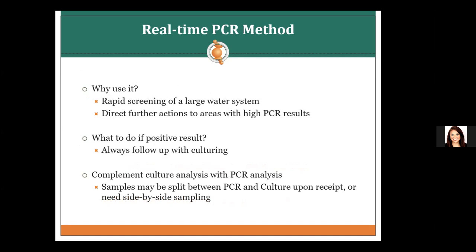People still use the PCR method because it is a rapid screening method for large water systems. For example, during an outbreak in a hotel with over 100 rooms, real-time PCR can quickly locate the contamination source. If there is a positive PCR result, it is usually recommended to follow up with culturing to determine whether the bacteria is alive or dead. Samples can be split in the lab or collected side-by-side for both PCR and culture methods.